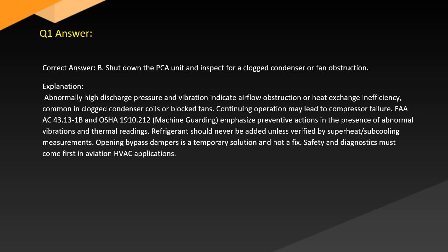Refrigerant should never be added unless verified by superheat and subcooling measurements. Opening bypass dampers is a temporary solution and not a fix. Safety and diagnostics must come first in aviation HVAC applications.